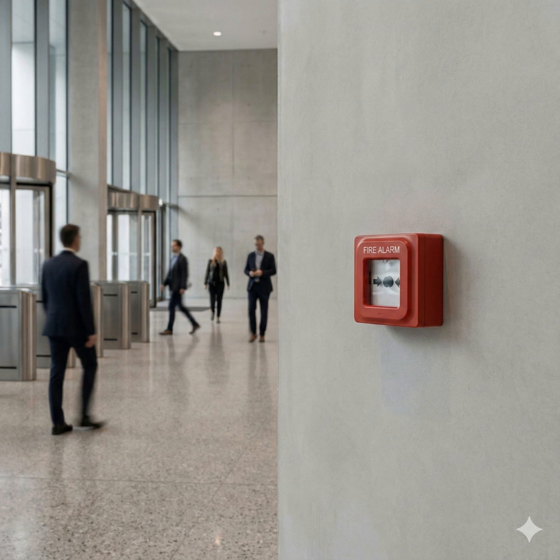And in modern high-reliability applications, you often see them combined, right? Yes, UVIR combination units. They require the presence of both specific wavelengths simultaneously for improved reliability, which drastically reduces false alarms. But I imagine that speed comes with a trade-off. What can fool them? The trade-off is susceptibility to non-fire energy sources. Welding, intense artificial lights, even direct sunlight can generate light in that same UV or IR spectrum, causing false alarms. This means you need a significant environmental safety analysis before you deploy them. Engineers have to confirm clear sight lines and make sure the device is carefully shielded from routine operational light sources.